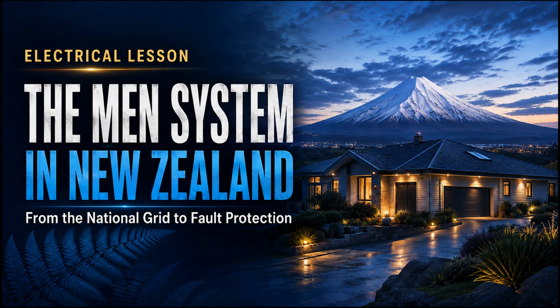S means that, within the installation after the MEN connection, the neutral and protective earth functions are separated into different conductors. The New Zealand MEN arrangement and the international TN-C-S arrangement are the same in principle, although the detailed rules and terminology are not identical. For New Zealand installation work, we use the requirements of the applicable New Zealand legislation, AS/NZS 3000, and the relevant distributor requirements. Next, let us walk through the main physical parts of the MEN earthing arrangement one by one.